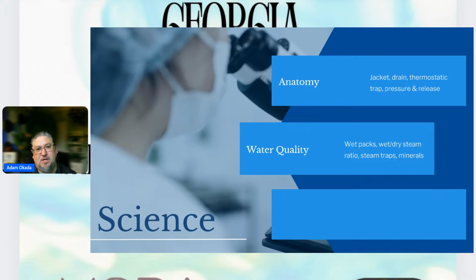So that wet to dry steam ratio, if you're having an hour of dry time... I actually had a hospital email us that had 90 minutes of dry time for their sets and they were still coming out wet. I said, it's the wet to dry steam ratio. It could be other things, like steam trap issues and other stuff, but it's more than likely issues with the wet to dry steam ratio.